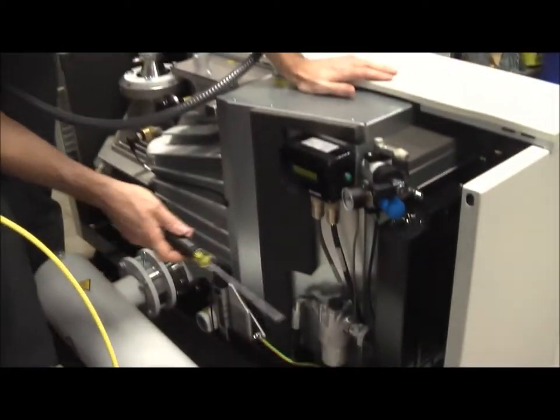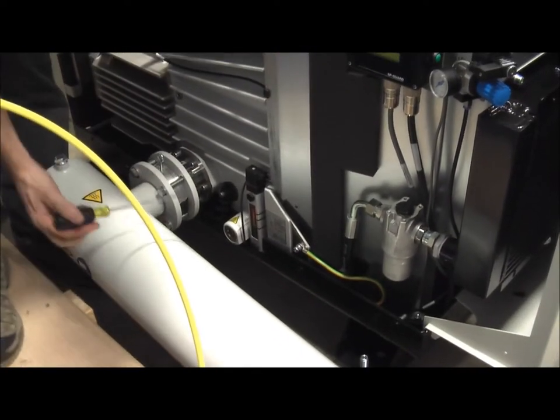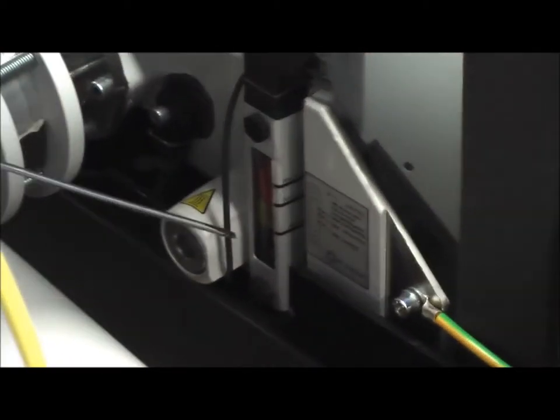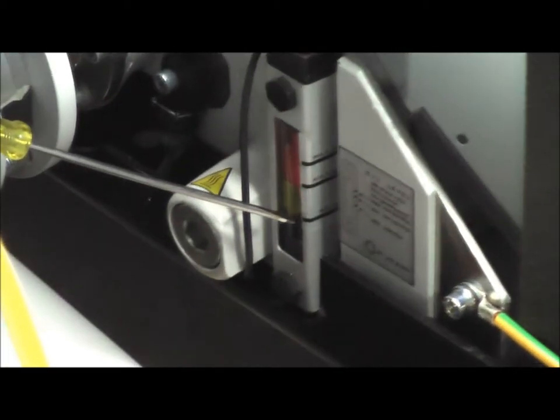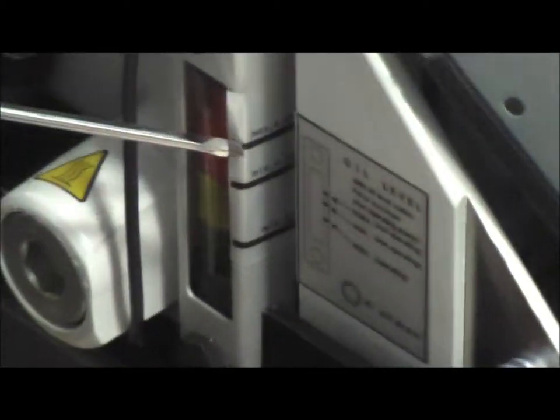It's got an oil cooler. The oil level is down here, so you want to check the oil level. It has three different marks: this is the maximum not operating and the minimum not operating, so it's right about here.